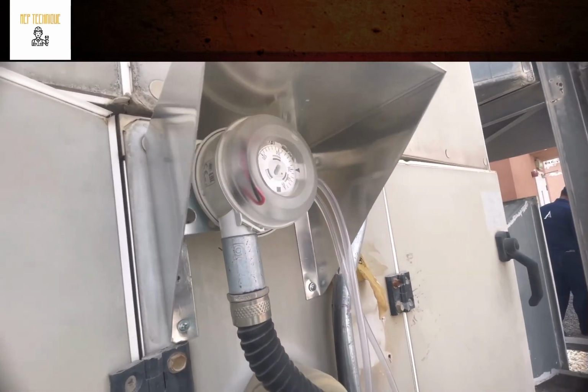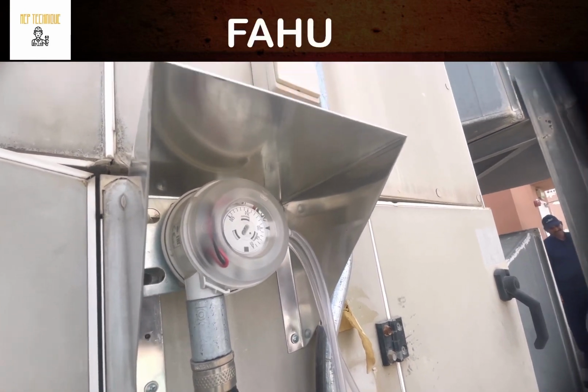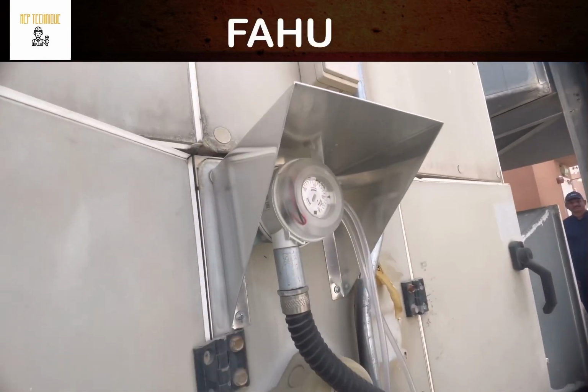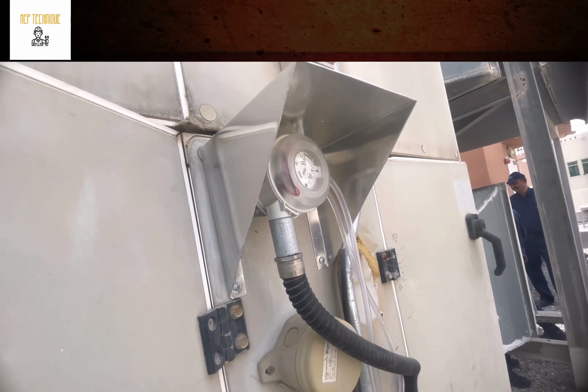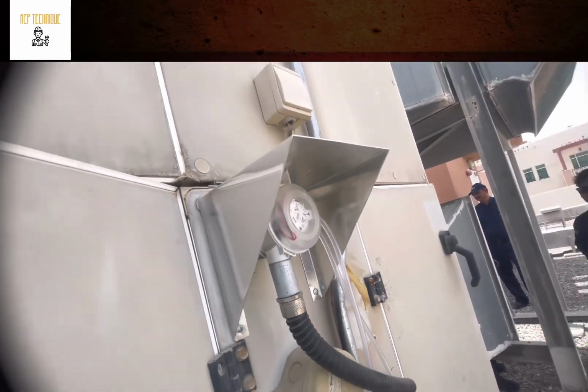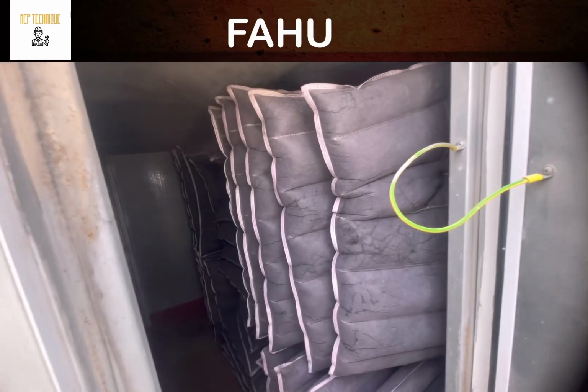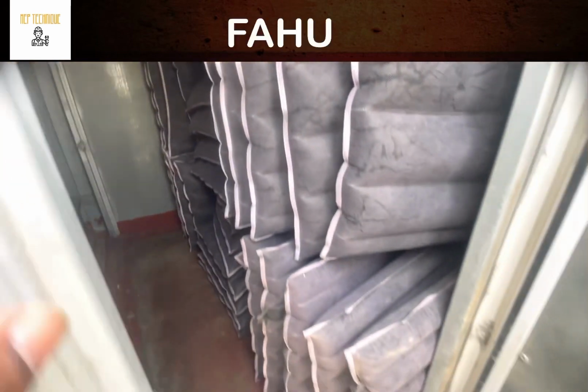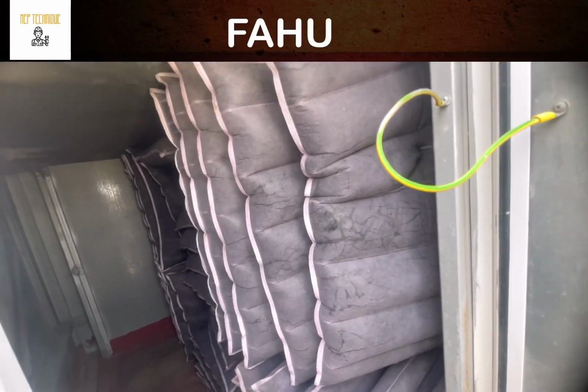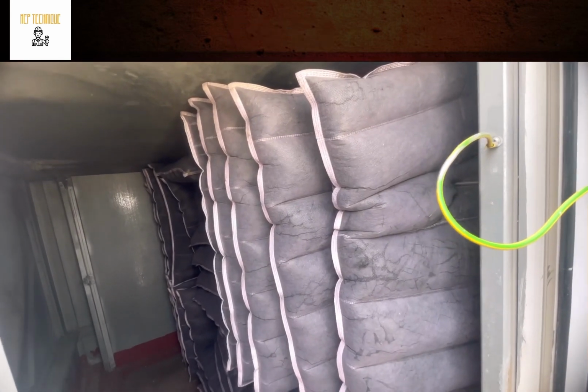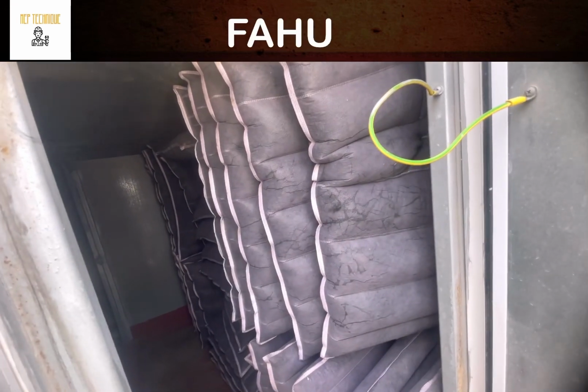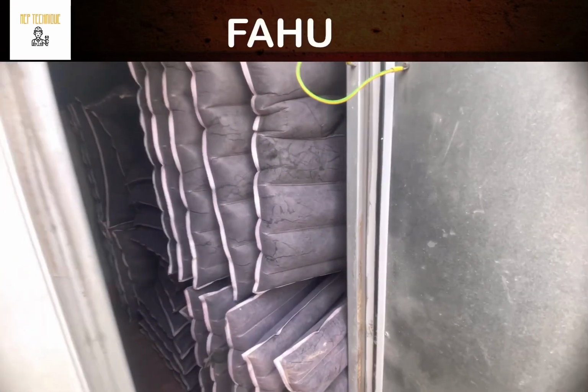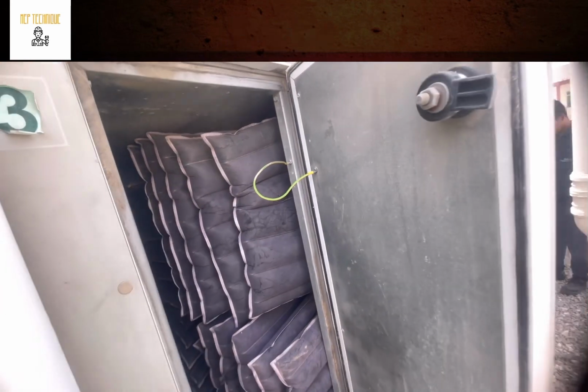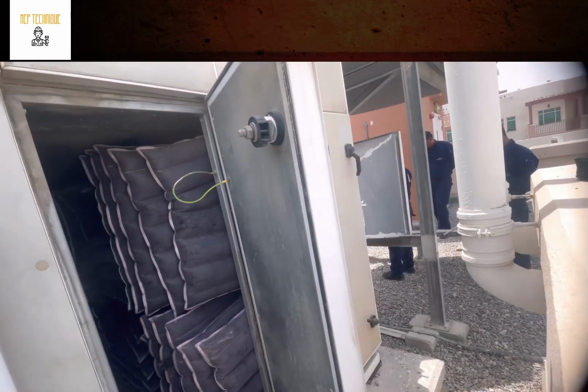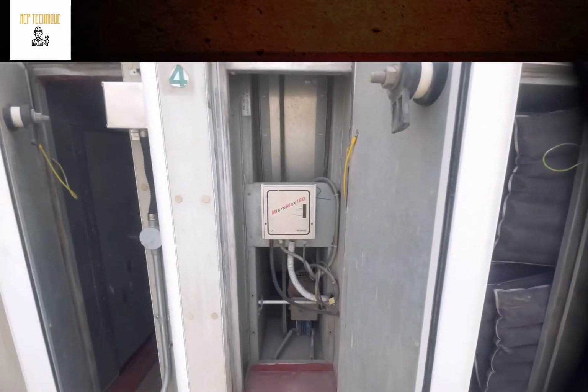It will monitor the filter, and it is integrated with our building management system. If our filter blocks, you will get to know by the BMS. Then this is our bag filter. The bag filter we cannot wash, it can only be changed, depending on the environmental factors and the usage. The efficiency of the bag filter is 65%. That means our bag filter can arrest 65% of the dust from outside.